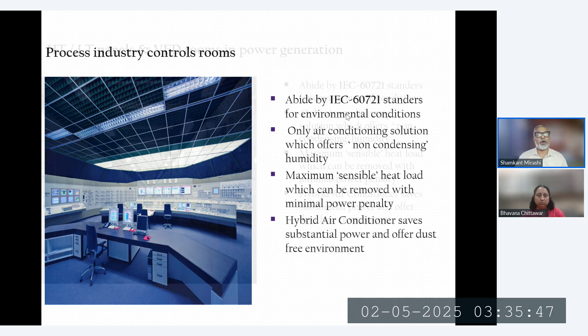Many times you'll see control panel rooms inside a process plant using air conditioning. These follow IEC standards, and we can proudly say that almost anywhere in India, we can comply with this IEC standard and still offer a very energy efficient cooling system for control room panels. Not only control rooms, but also cooling of HT/LT panels.